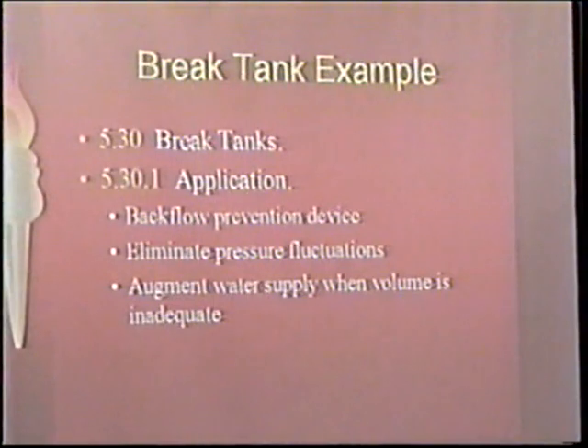Now we're into that break tank. It talks about the application there. The backflow prevention device does provide a break between the city water supply and the fire pump. It talks about how it eliminates pressure fluctuations. What Ed was alluding to there is if you have a city water supply that has a normal static of, say, 50 pounds, but during the night you can get some big fluctuations, where you've got a sprinkler system designed basically for your lower static water level, and you've got a big surge that can occur in there, and that's going to put you over the rating for the system components.